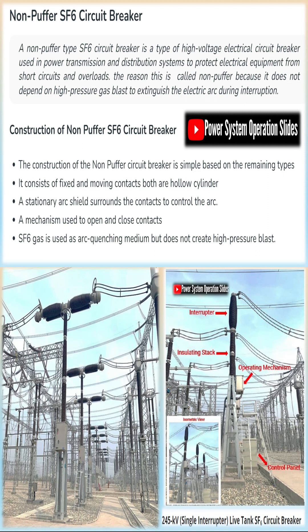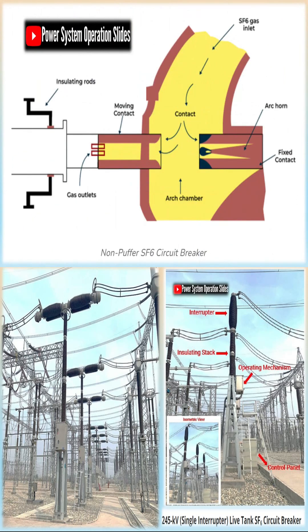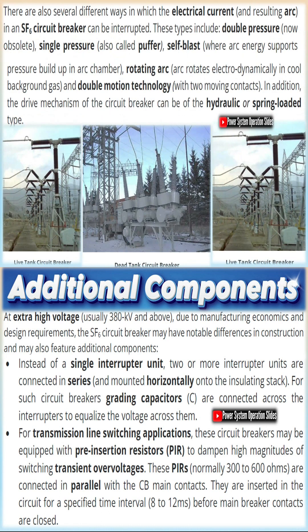These breakers are composed of several main components: the interrupter unit, where the arc interruption takes place using high-pressure SF6 gas; the insulating stack or bushings that provide insulation and mechanical support; and the mechanical operating mechanism that drives the opening and closing of contacts, typically using spring or hydraulic power.